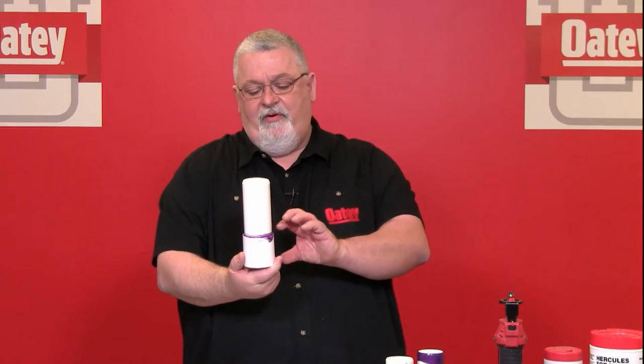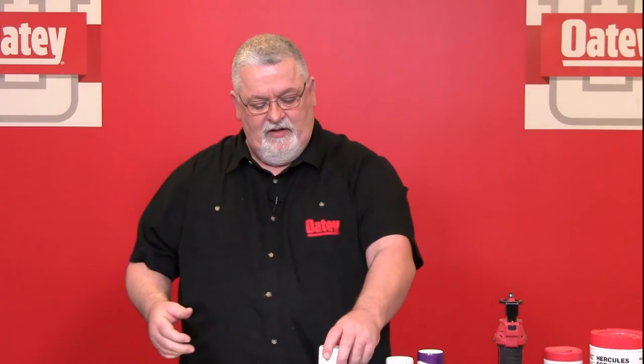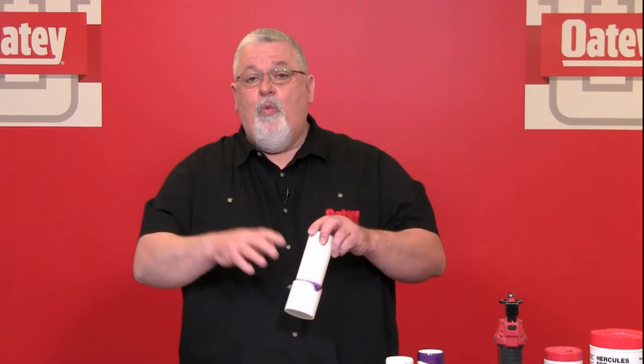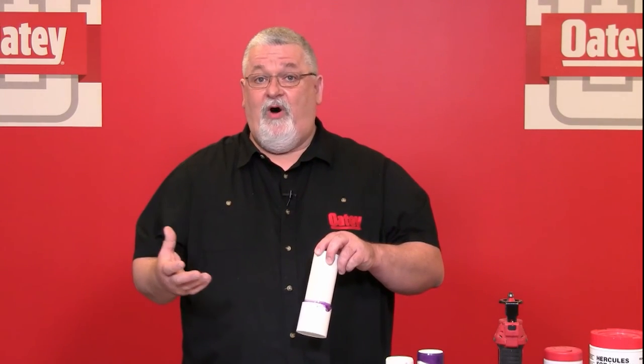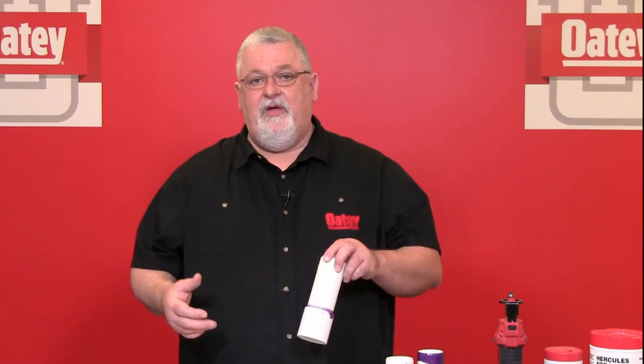The set time starts after assembly. Set time determines when I can move the joint around or add another piece of pipe to the system. It's completely different from cure time, which determines when I can pressurize the system to test it with water or initiate service. Those are two very different timeframes. We have literature online at Oatey.com where you can find the cure times and set times at any time.